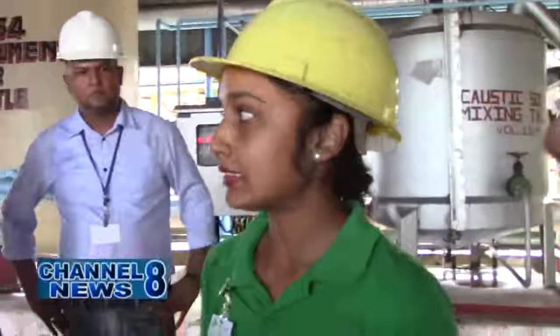We have suppliers as far as from Mara to Berberoela. Farzana Hakim, chemical water treatment plant manager trainee, explained the importance of this plant in the production of electricity. Basically, an immense amount of water is needed daily for the boiler and co-generation power plant operation. However, it requires good quality water for safe and reliable operation. The water being collected from the GWI contains various levels of contaminants, dissolved solids and dissolved gases, which can cause problems to equipment used in our power plant and to the boiler. So the chemical water treatment plant provides a filtration mechanism for these impurities to control and remove them on a continuing basis.